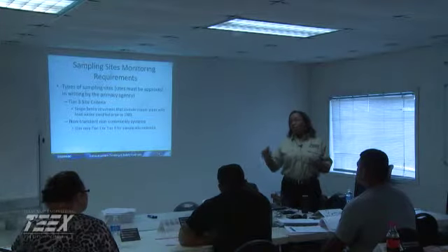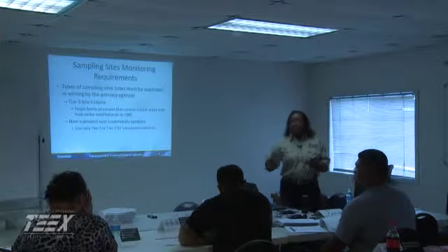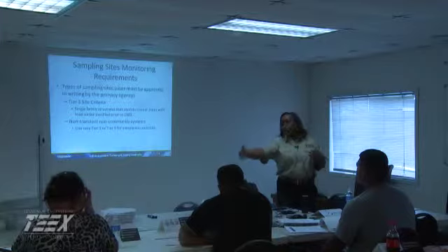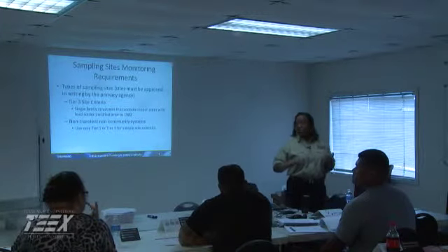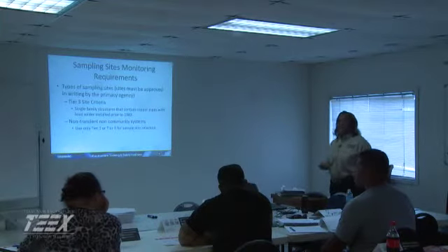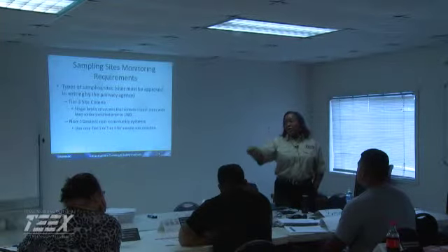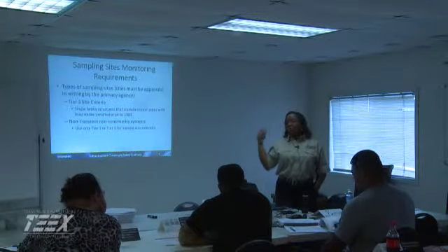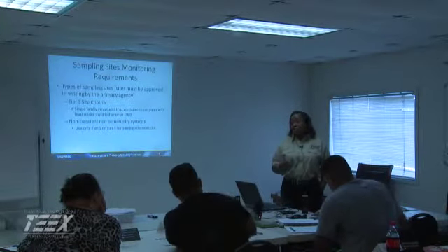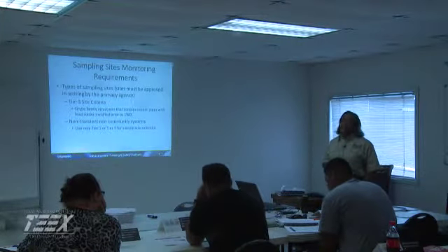You can initiate the process of getting a waiver or an exemption. It does not exempt you totally from doing it, but it does give you a wider frequency of doing the analysis. Okay? So you can apply for an exemption in cases like that. When you can prove it, you have to do the process of proving we have no copper pipes or we did not use lead, solder, and flux in our plumbing systems. And once you can prove that, you can apply for the exemptions. They give you that option to do that.